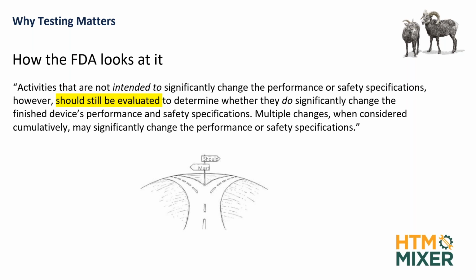So it's not enough just to say, and some third-party guys, we've seen in documentation where they would say, yeah, we didn't do anything significantly different. The FDA doesn't care. They want to know, did you validate that activity you performed on this medical device to show objective evidence that it is substantially equivalent to the OEM one? So they look at not what somebody says, but what their activities are, okay? And how they look at that. So they put this up there. They should still be evaluated whether they actually do significantly change the device's performance and safety specifications.